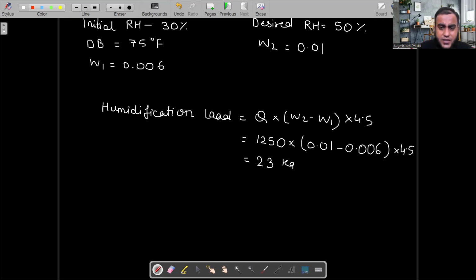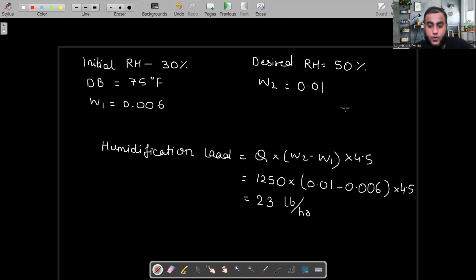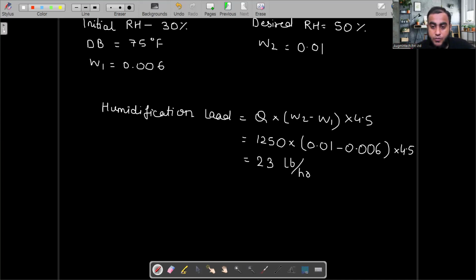And the unit is, remember, kg per hour. Sorry, not kg, pounds per hour, okay? Everything we have taken in pounds per hour. It means 23 pounds per hour means the humidifier which you are using needs to add 23 pounds of moisture, water vapor content, in 1 hour, to get how much humidity? 50%. So 23 pounds per hour. They can add 23 pounds of moisture in 1 hour to get the desired relative humidity of 50%.